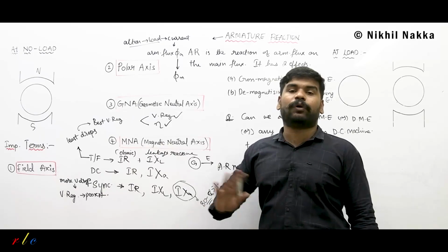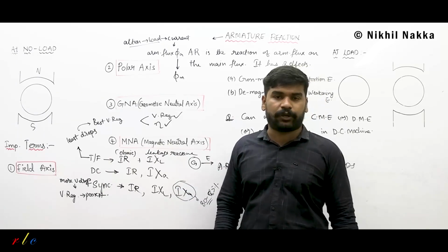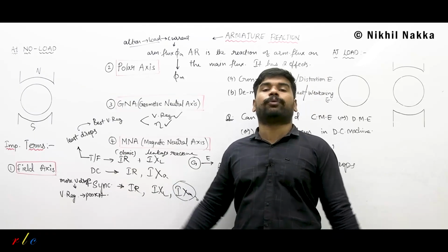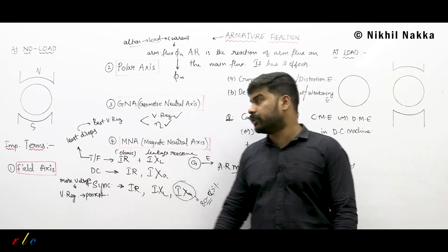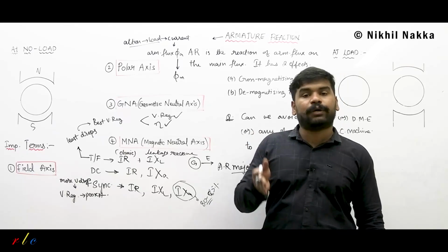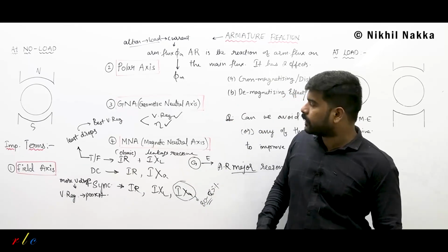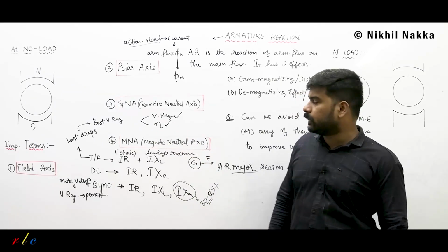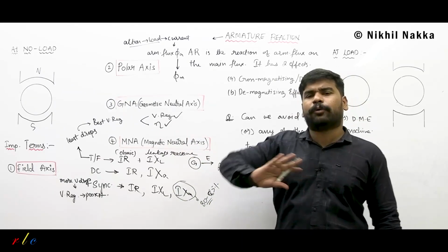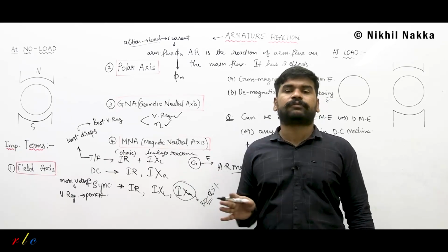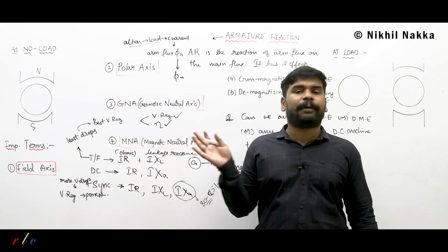When you say high voltage regulation, it signifies a very wrong sense. High voltage regulation means more voltage drops, more variation, more fluctuation in the voltage. Numerically, good voltage regulation should be the least value. And technically, a transformer's voltage regulation will not be more than 10% even in the worst case.